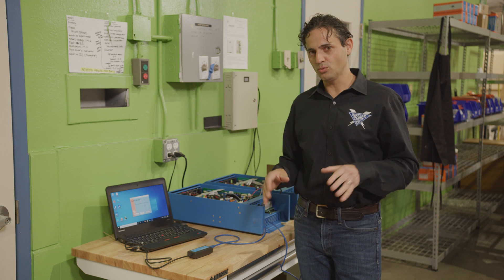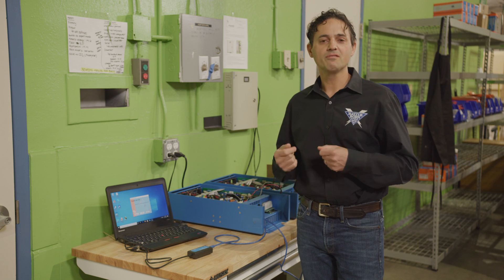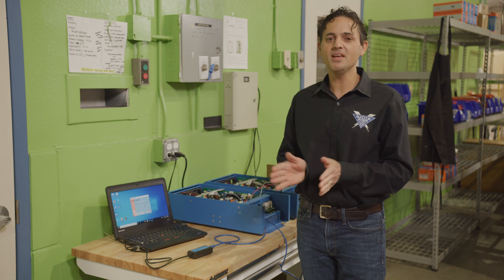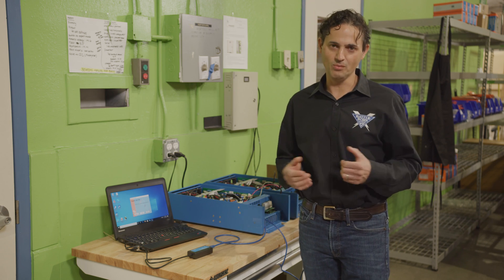There are some special cases where you could actually accept 120 volts from a generator with two legs and use an auto transformer to make those into split phase, creating a 240-volt system with two Multi-pluses.